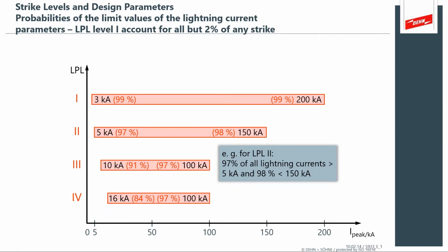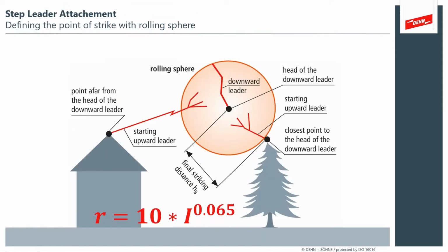If you have something like a steel building and the contents are not particularly valuable, then you can tolerate more risk, and you can tolerate an LPL 3 or even LPL 4 type system, where you're accommodating a narrower range of lightning strike incidents. A chart like this shows you the high levels of lightning and also the low levels of lightning. And that low level of lightning is what's important when we're discussing the rolling sphere.